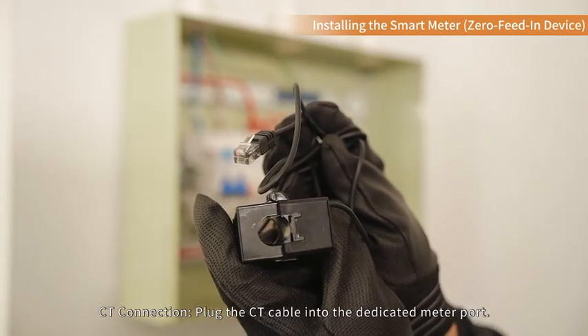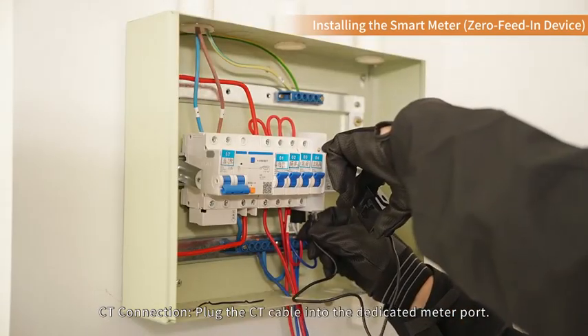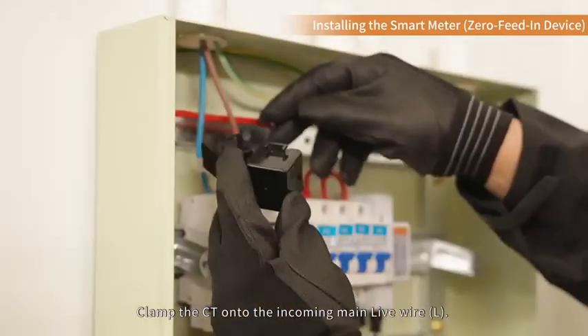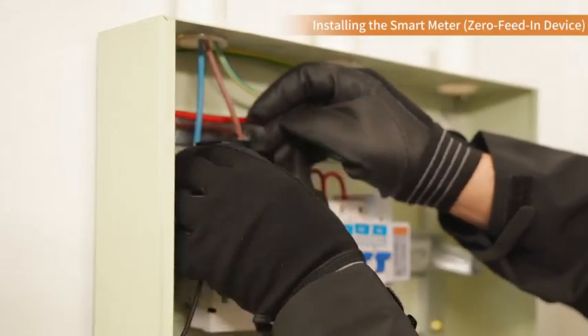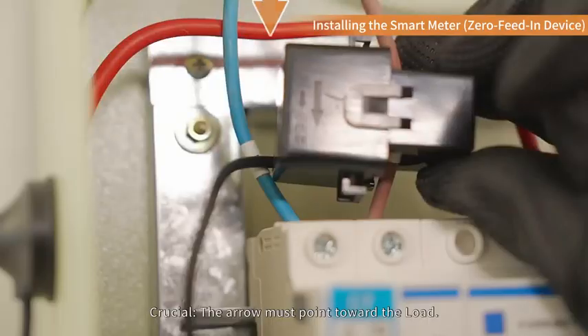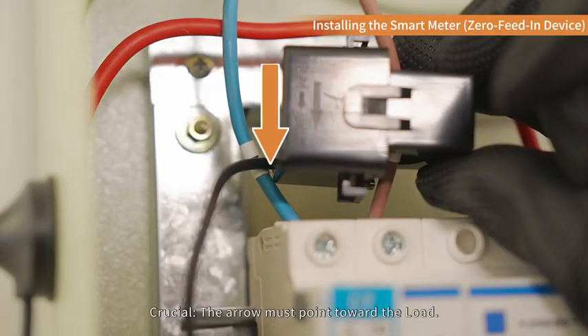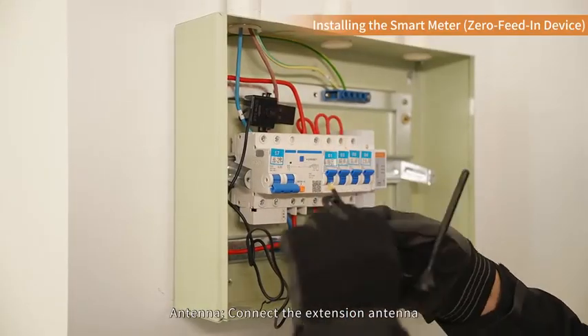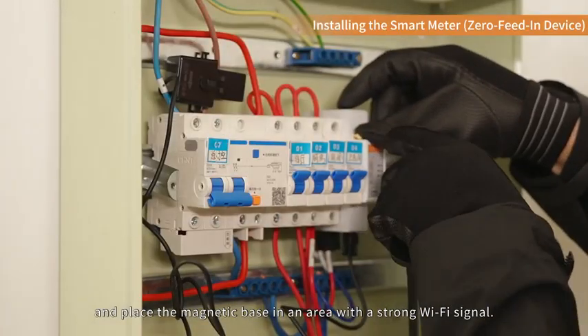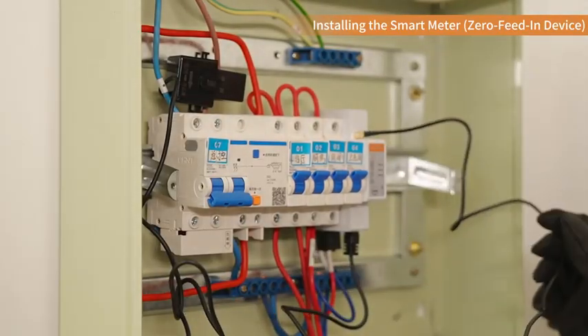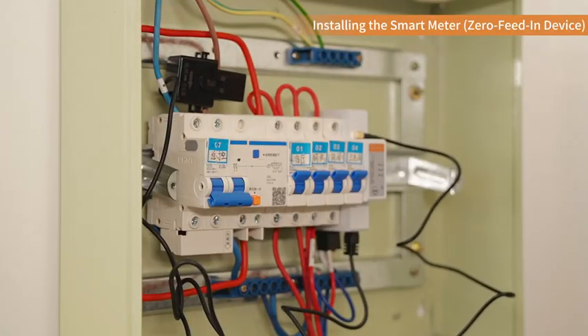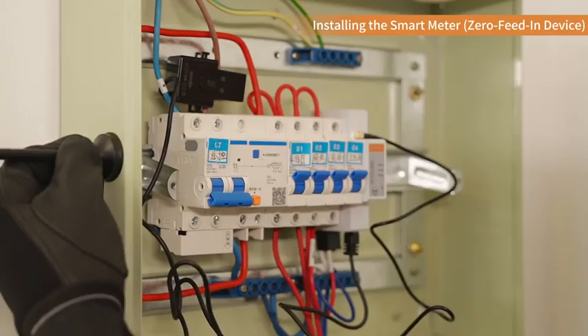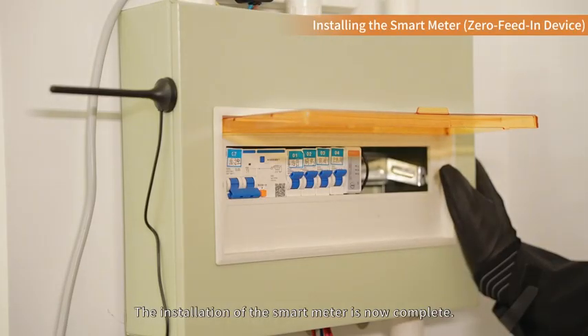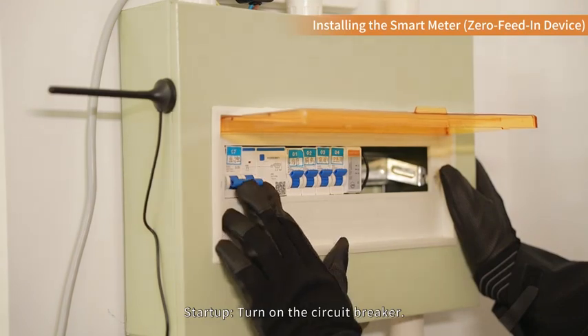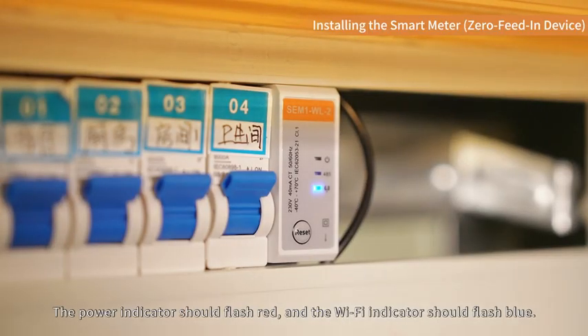CT connection: plug the CT cable into the dedicated meter port. Clamp the CT onto the incoming main live wire L. Crucial: the arrow must point toward the load. Antenna: connect the extension antenna and place the magnetic base in an area with a strong Wi-Fi signal. The installation of the smart meter is now complete. Start up, turn on the circuit breaker. The power indicator should flash red, and the Wi-Fi indicator should flash blue.